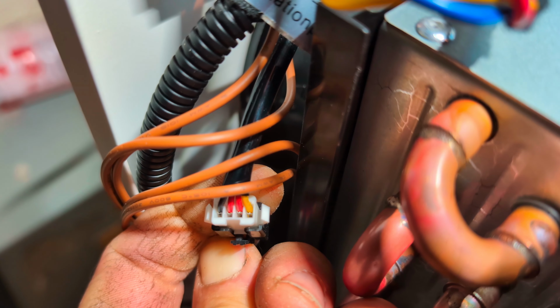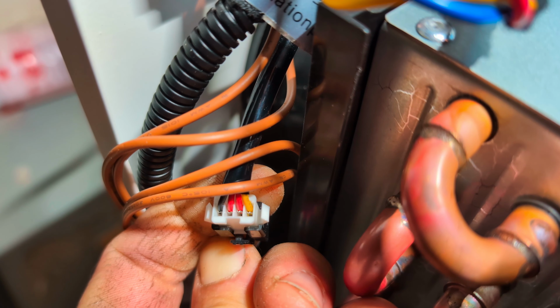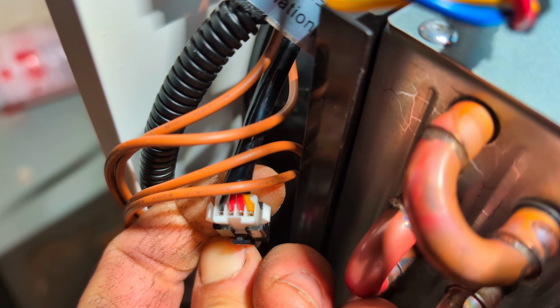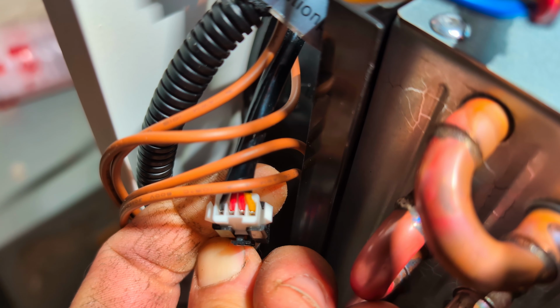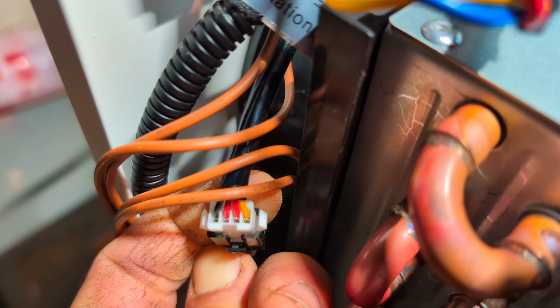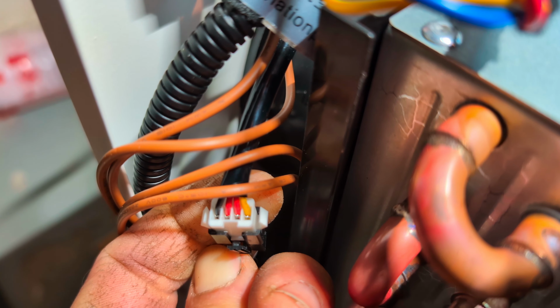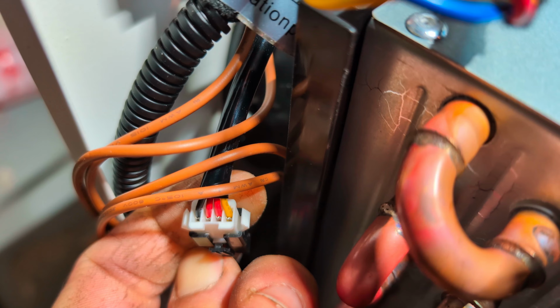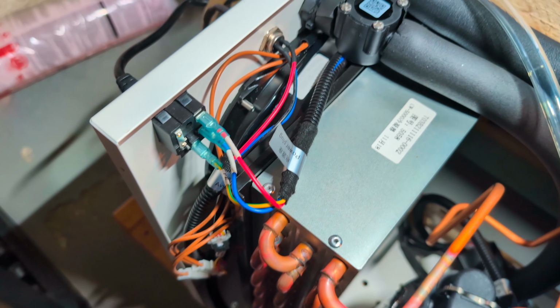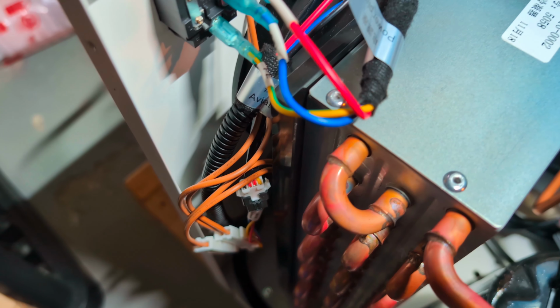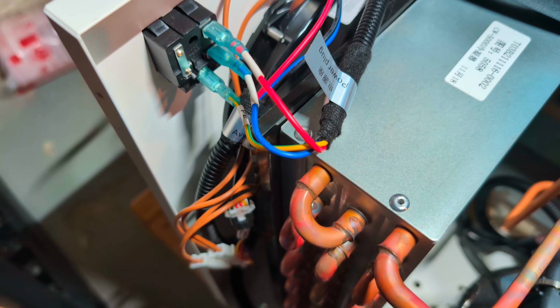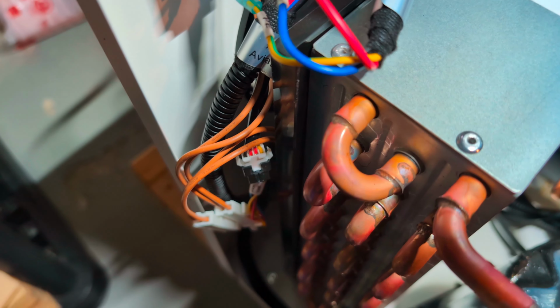I was getting 0 volts, 0.01 volt from the yellow to red. That's the output. And what happens is if you're not getting an output from the flow switch, then the water chiller does not recognize that there's a flow, and then the alarm will sound and it will not allow you to go any further. So I found that there was 0 volts from the yellow to red wires when I tested with the multimeter.